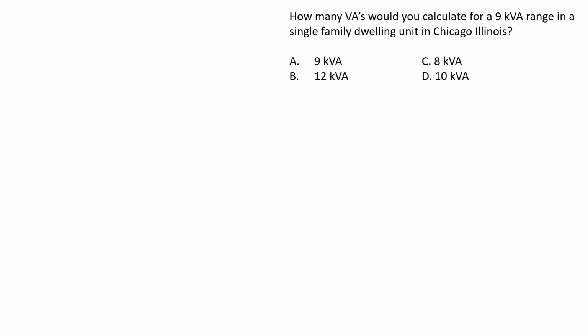So you would take one range, and say it was 5 kW. This table is saying that you would apply an 80% demand factor. You would use column B and you would use one appliance. So you would use one appliance, slide over to column B and multiply it by 0.80.